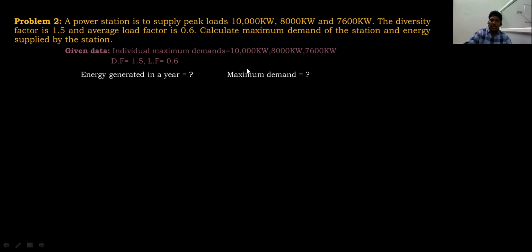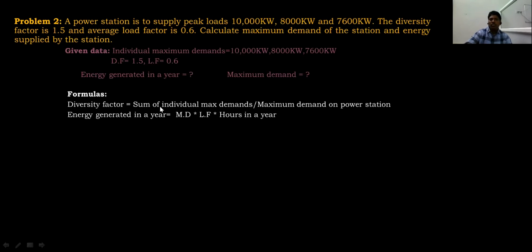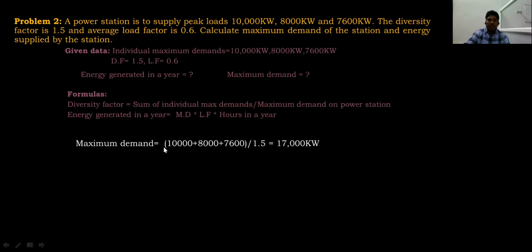The individual maximum demands, diversity factor and load factor are given, and we need to find the maximum demand as well as the energy generated in a year. The formula is diversity factor equal to the sum of individual maximum demands divided by the maximum demand on the power station. We already know this formula from the last video. Therefore, 1.5 is equal to the sum of individual maximum demands, 10,000 plus 8,000 plus 7,600, divided by the maximum demand. Taking the maximum demand to the other side, the maximum demand is equal to this divided by 1.5, which is equal to 17,000 kilowatts. From the diversity factor, I have found the maximum demand.